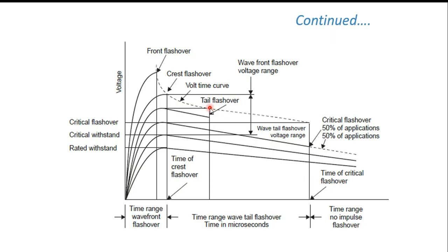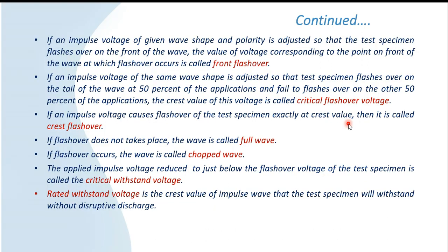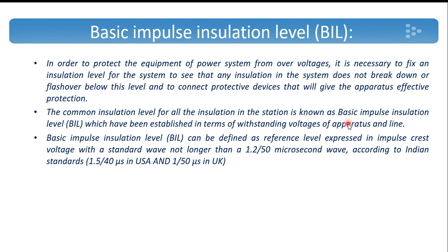In order to get the insulation strength of the equipment, different waves of the same shape but different peak values are applied and the flashover voltage and time are measured. The volt-time curve is then drawn and the critical flashover voltage is found out.